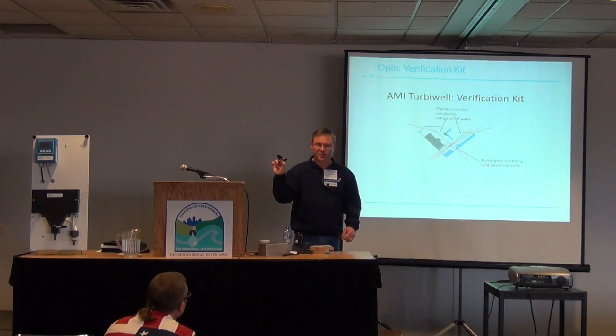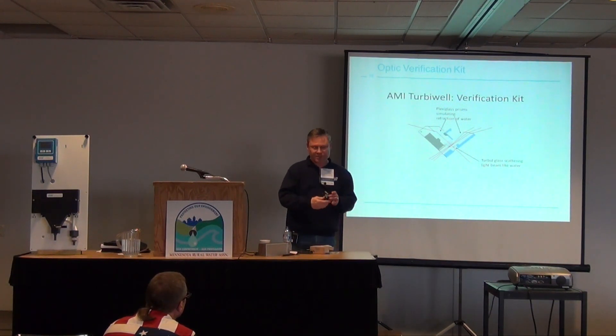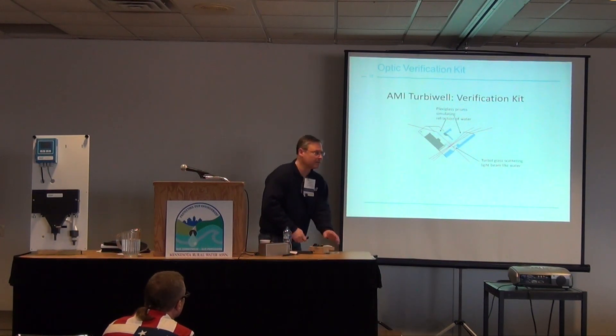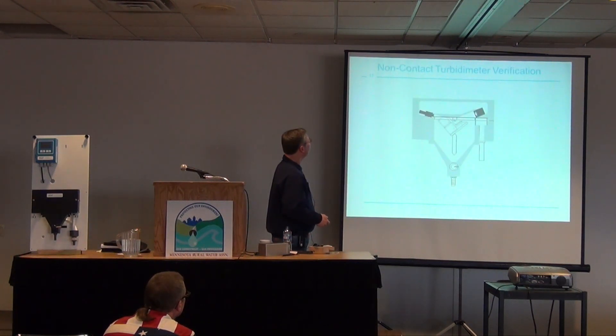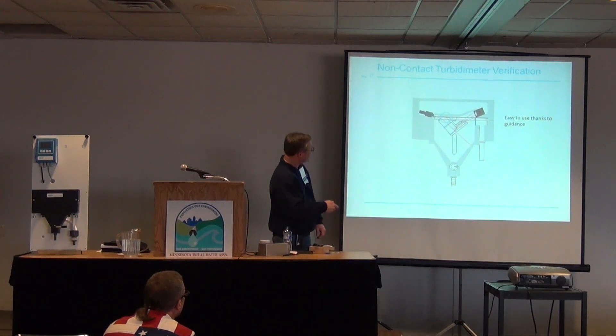Each verification kit has an individual QA value from Swan. People ask if we can recertify these — the answer is yes, but you really shouldn't have to unless you drop it. There's a little locking piece and it literally just fits right into the instrument perfectly.